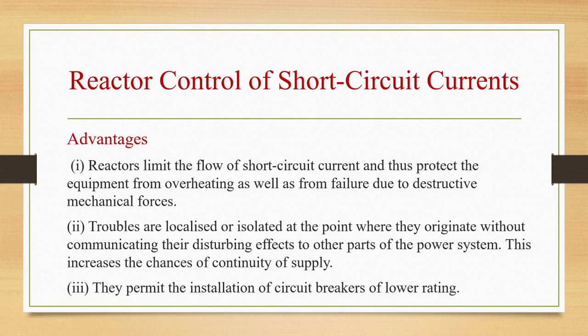Let us see the advantages of these reactors. Reactors will limit the flow of short circuit current and thus protect the equipment from overheating as well as from failure due to destructive mechanical forces. Second, troubles are localized or isolated at the point where they originate without communicating their disturbing effects to other parts of the power system.